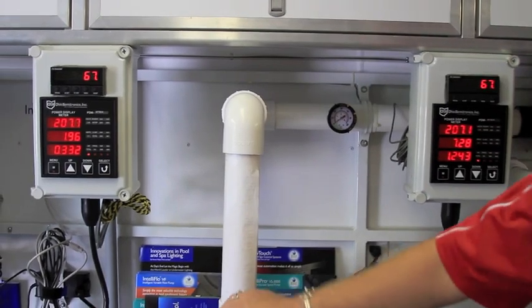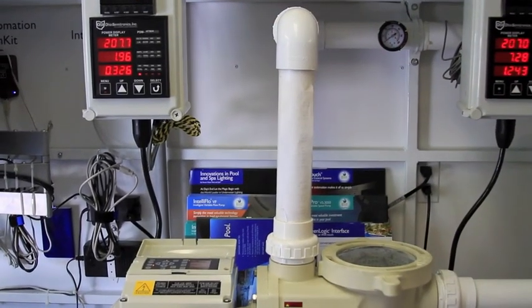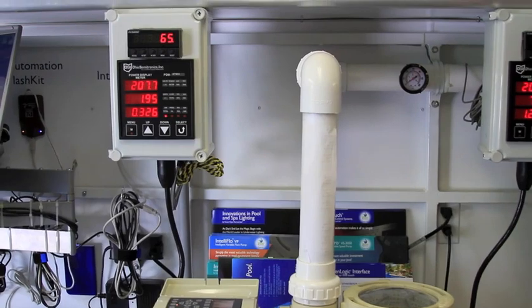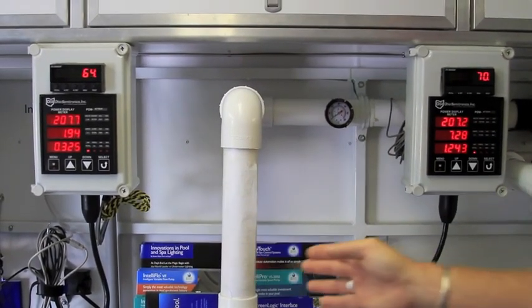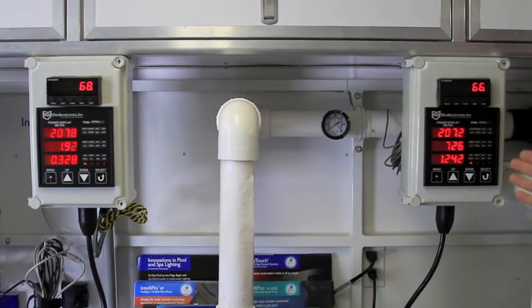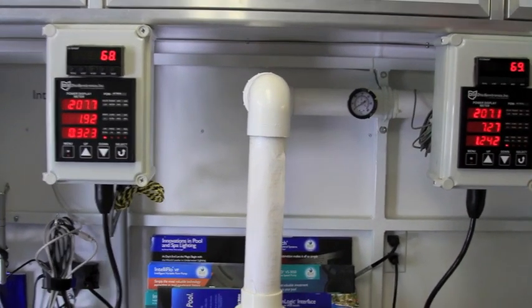And what we're showing here is the kilowatts being used by the standard efficiency pump at roughly 1.24. And here on the IntelliFlo, flowing the same rate, is 0.3. So you can see that the IntelliFlo is using four times less energy than the standard efficiency pump.